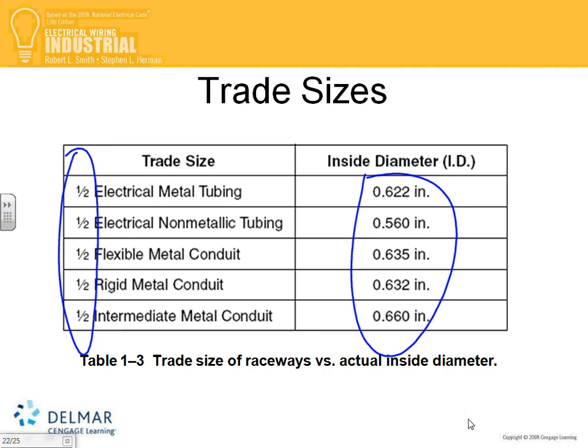Flexible is different. 1/2 inch, all of them, look at this, 0.62, 0.5. Rigid, flexible, PVC, we don't have PVC, but intermediate metal conduits, rigid metal conduits, flexible, these are all metallic. Non-metallic, here you go. Electrical non-metallic tube, that's an ENT, 0.56. That's the smallest, right? It makes sense if you look, this is non-metallic. Anyway, that's a trade name, not an actual interior diameter.